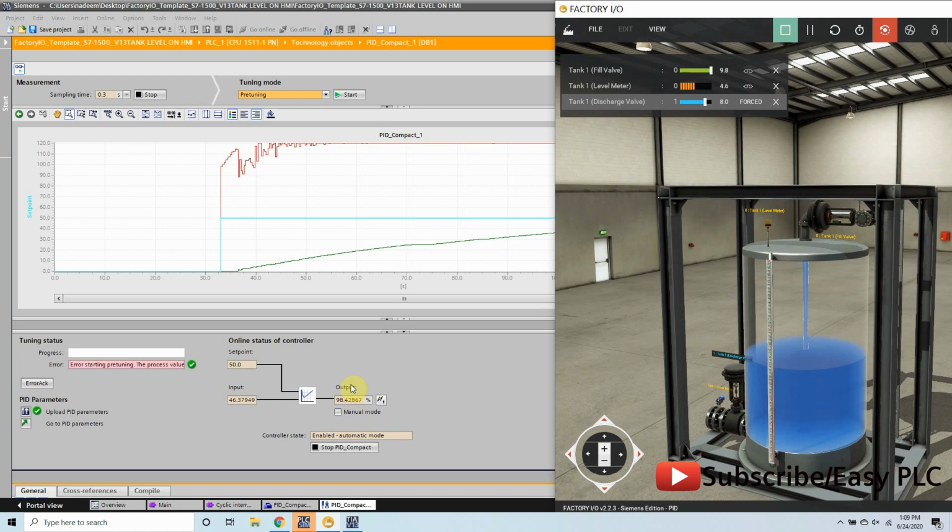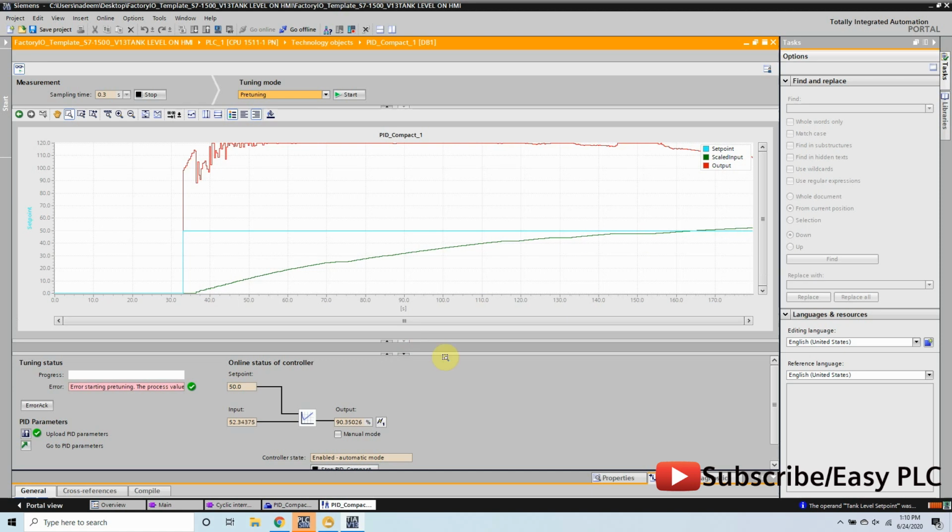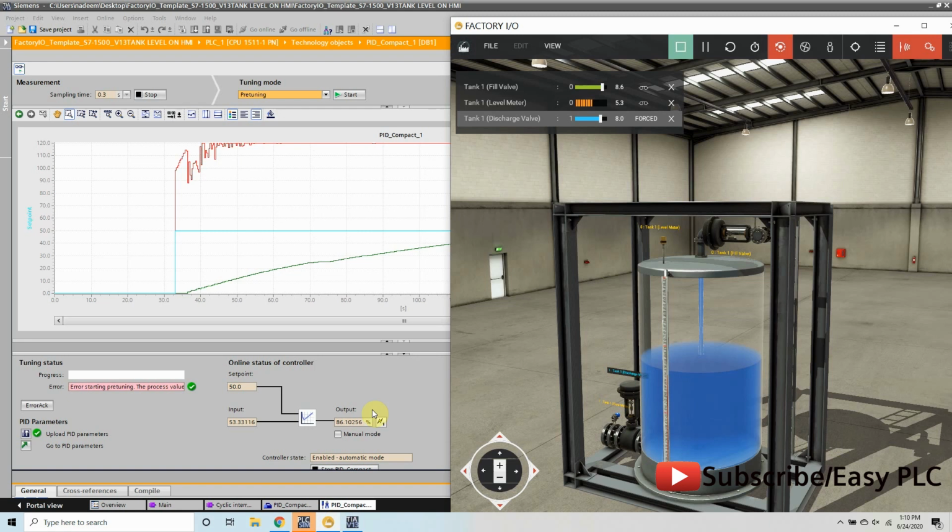As you can see, once the tank level has reached 45%, the PID output starts to decrease gradually, to make sure that it will reach 50% tank level smoothly. Now the tank level is above 50% and the PID output control signal is decreasing at a faster rate, so as to keep the error, or difference between set point and actual tank level, not more than 2 or 3%.